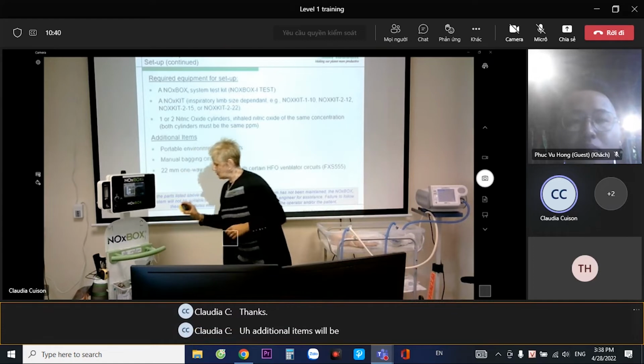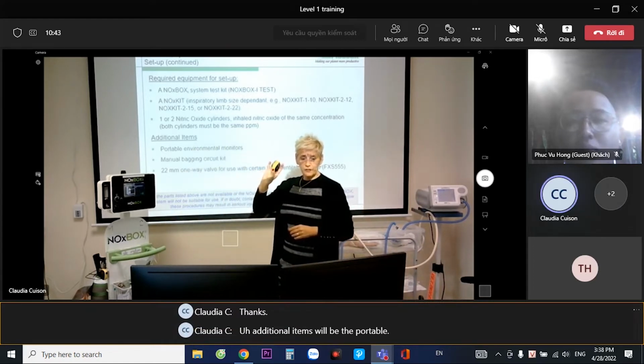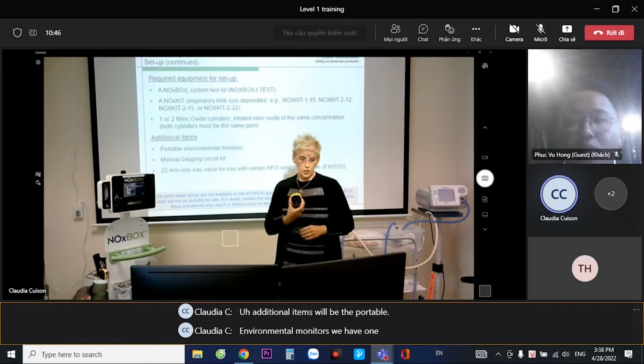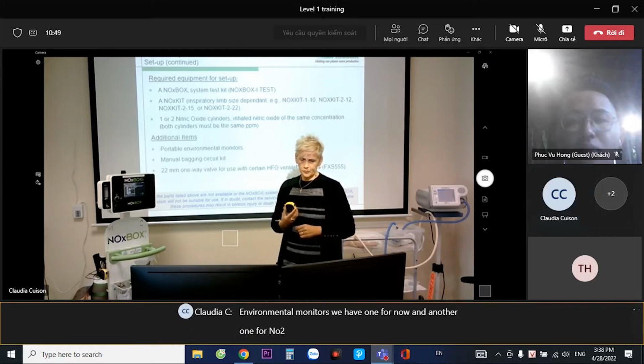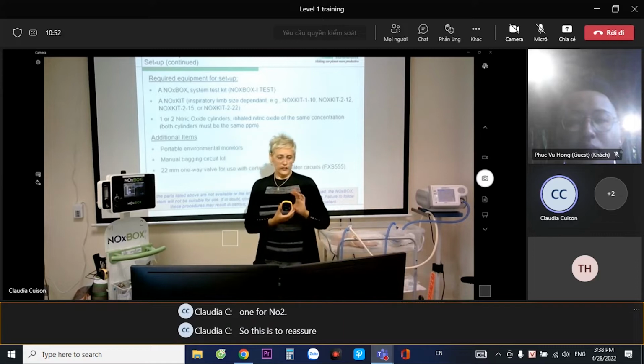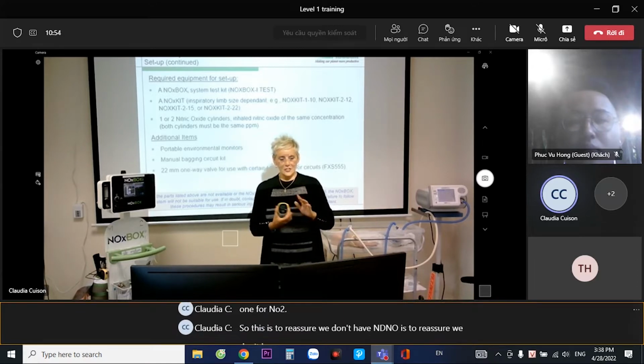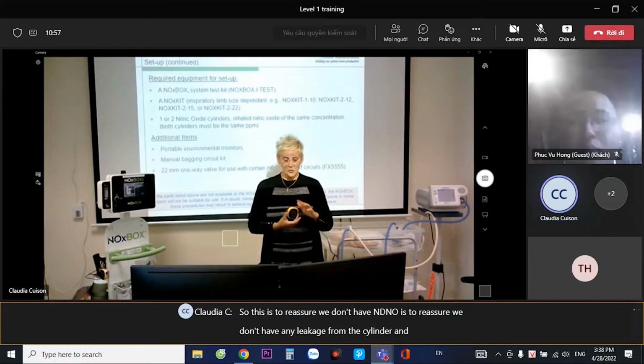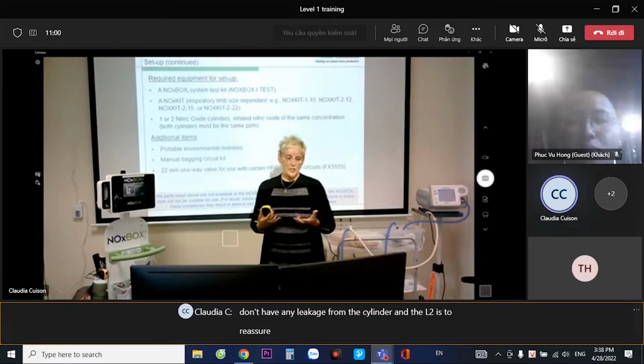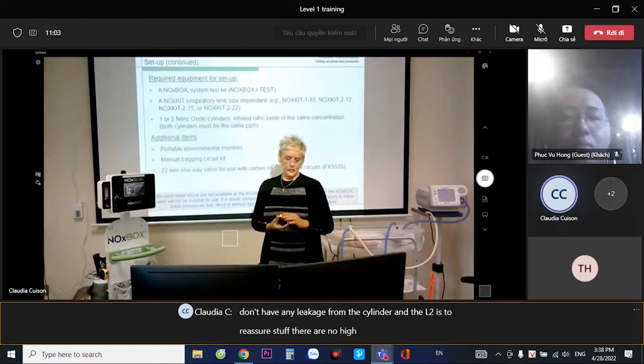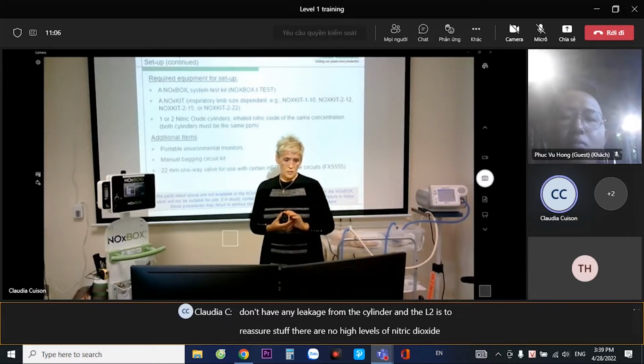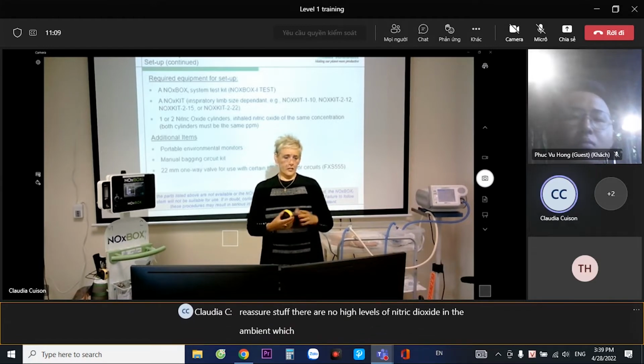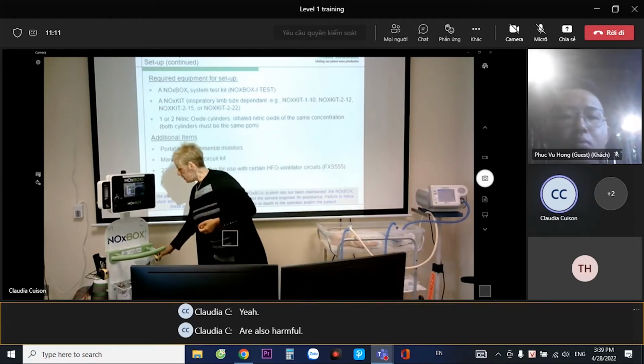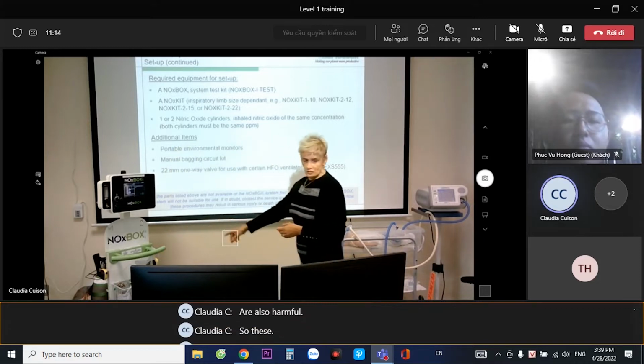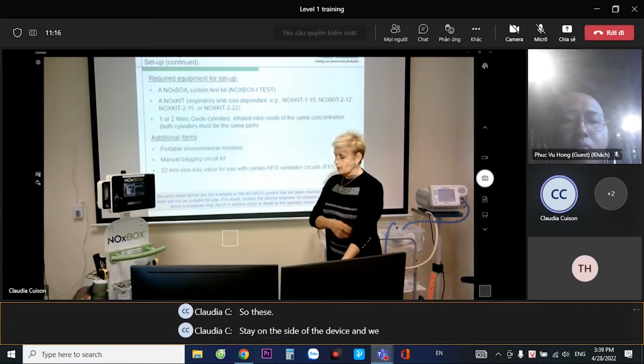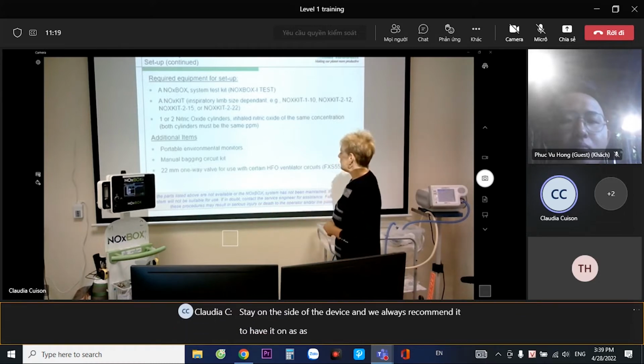Additional items will be the portable environmental monitors. We have one for NO and another one for NO2. The NO monitor is to reassure we don't have any leakage from the cylinder, and the NO2 is to reassure staff there are no high levels of nitrogen dioxide in the ambient air, which are also harmful. These stay on the side of the device, and we always recommend having it on as they are now.